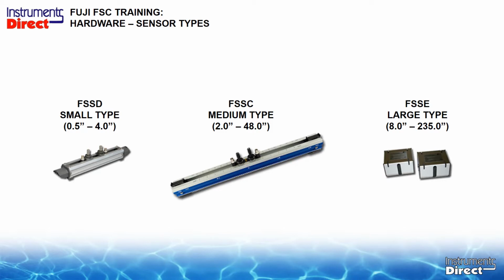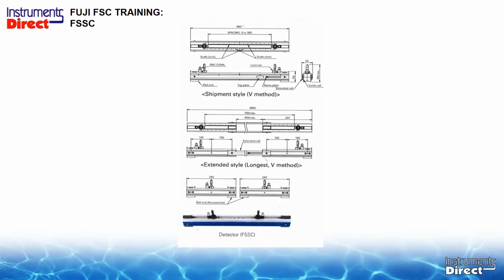As we indicated, the FSSC is quite a novelty transducer, and it is a 1 megahertz transducer. It has a slightly different crystal angle, so that's why we need to update the firmware as opposed to the traditional 1 megahertz, the 31, the 11, 41, and so on. This one's kind of unique. The overall length of the rail itself is 18 inches from end to end when it's compacted. For larger pipe sizes, you remove a few screws and it telescopes over to 34.6 inches in length. It just slides out and makes it longer. Then, if you have a very large pipe application and you need to use the Z configuration, you remove the blue rail and then you will actually have 2 separate rails with transducers on it, one on each side of the pipe, and each one will be on a rail in itself, which makes that large pipe application installation very much easier.